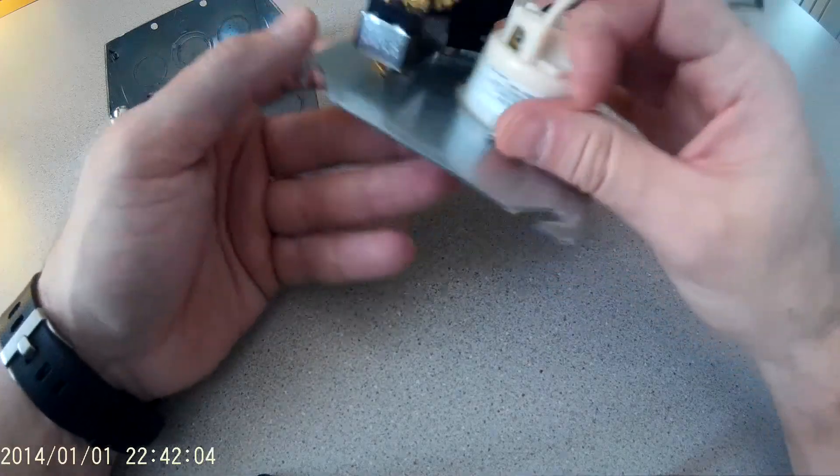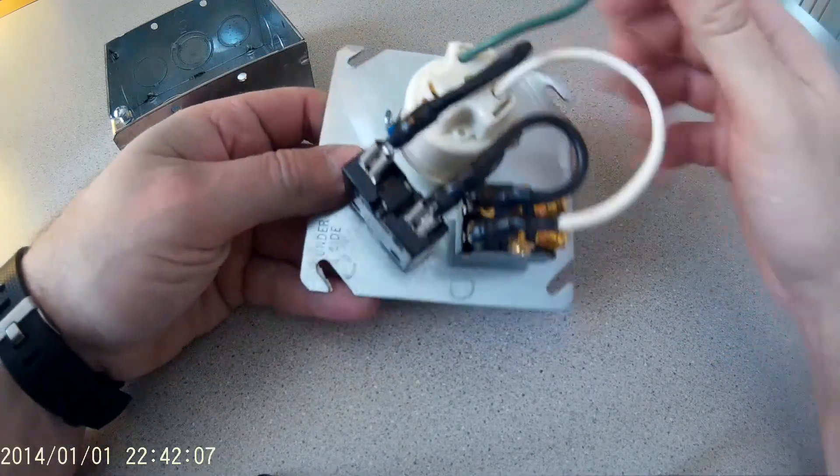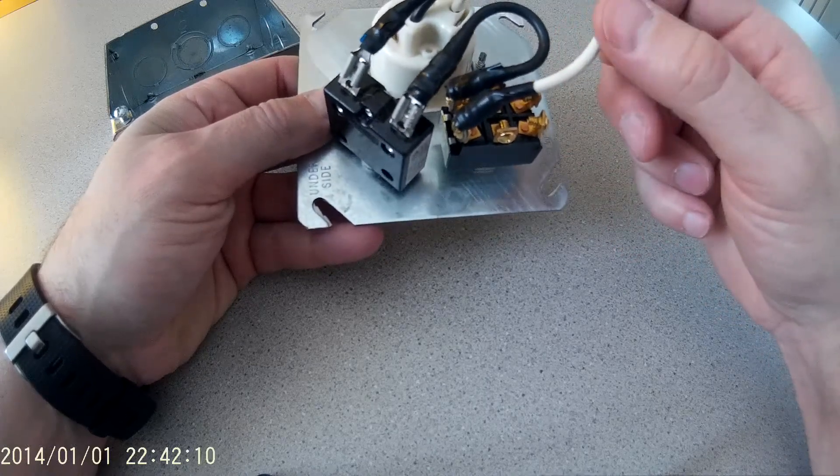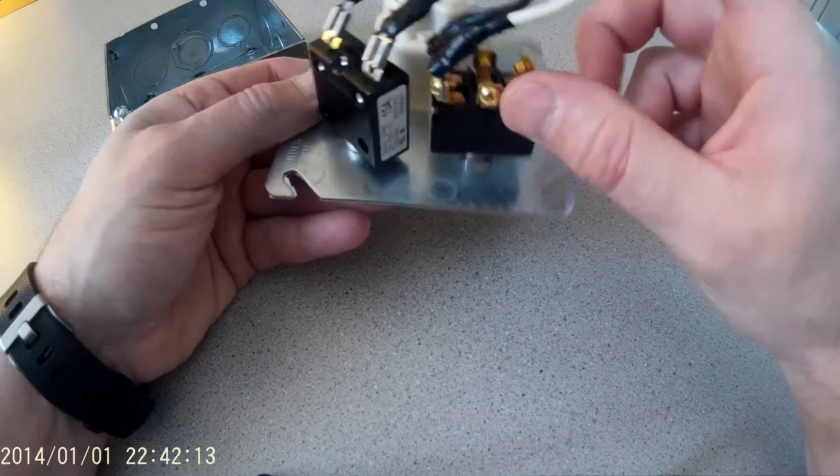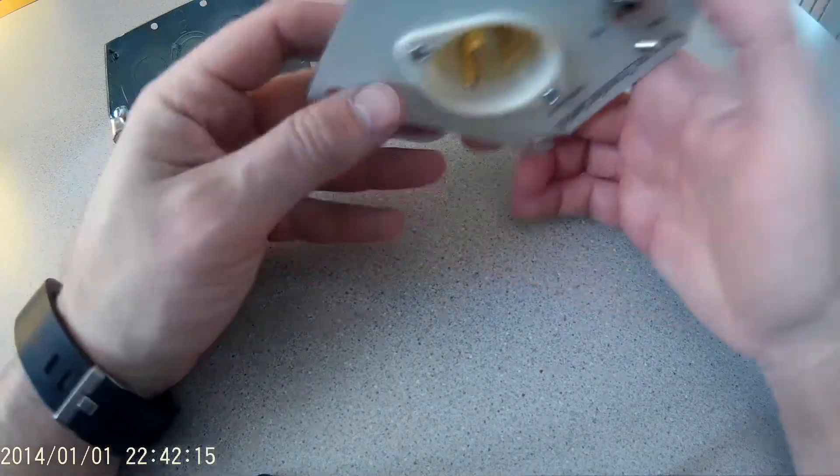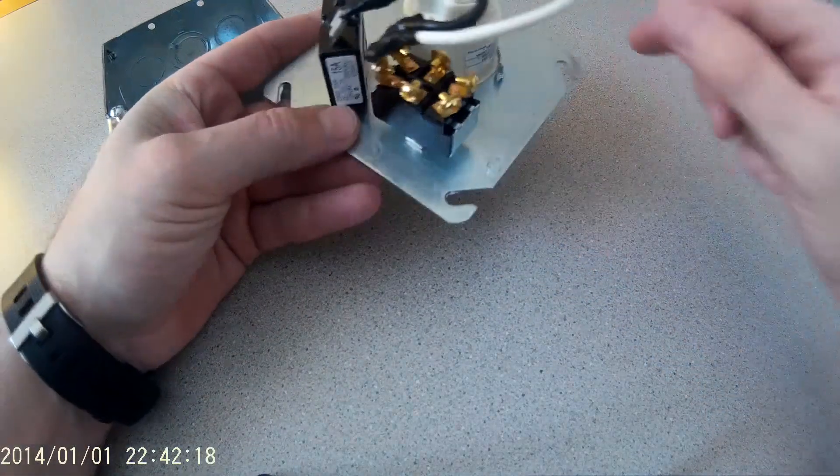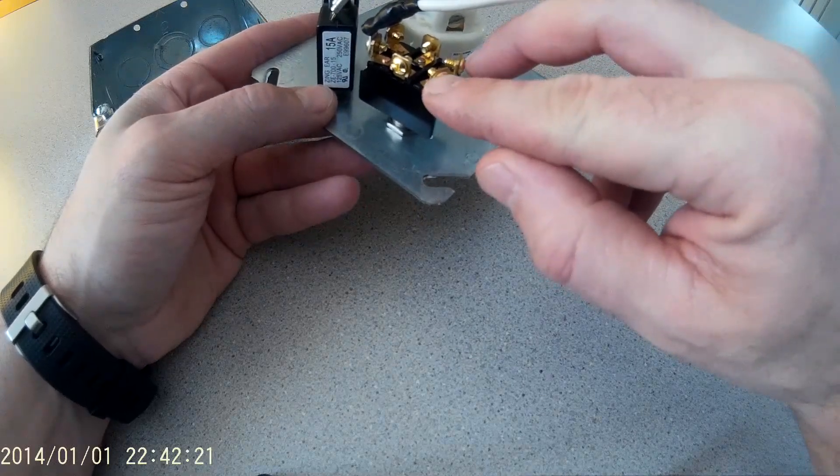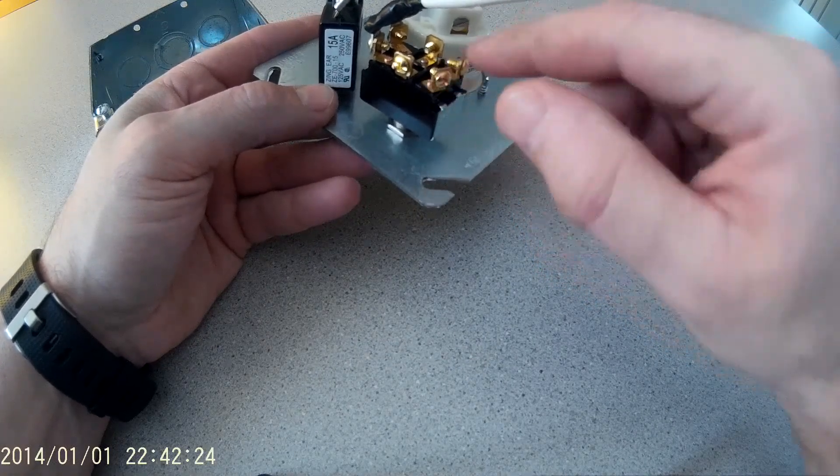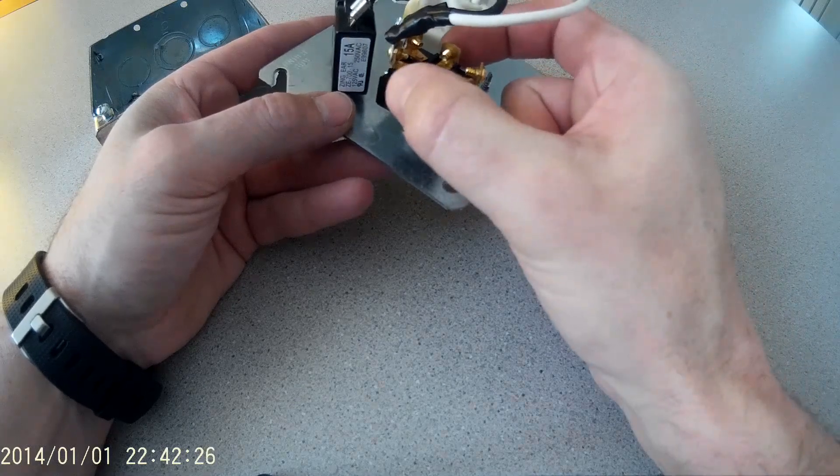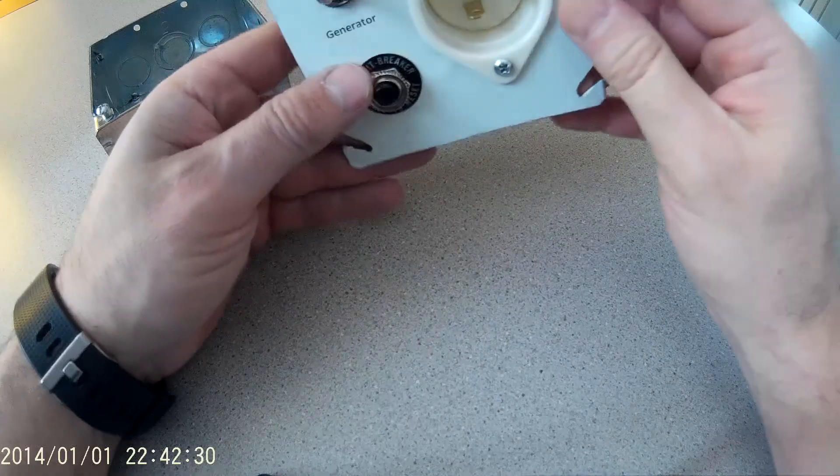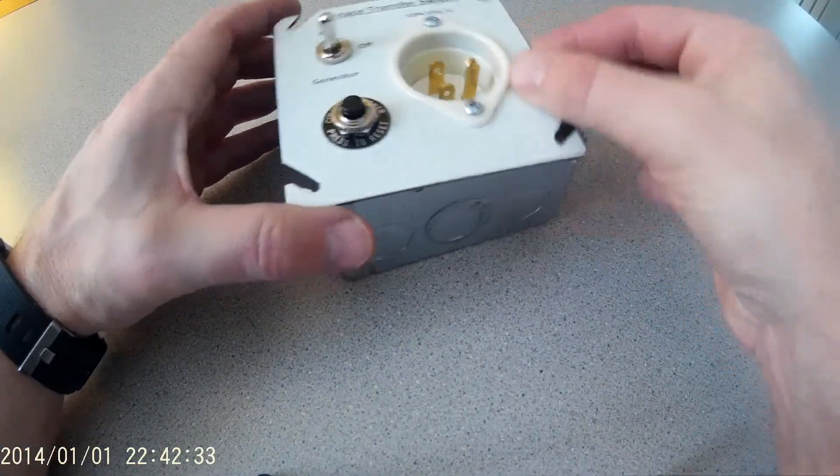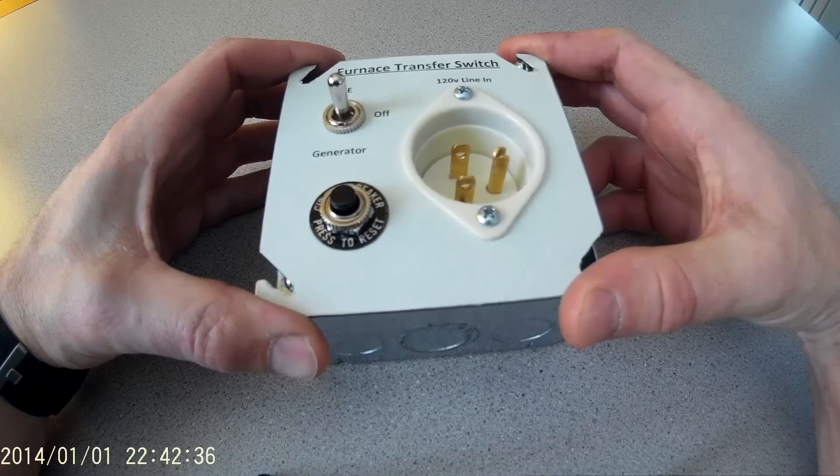On the back, you can see I just got a ground wire. Our neutral goes right to the double-pole, double-throw switch, and the hot wire is running through the circuit breaker. So all I'm going to do is wire in my line hot and neutral to these two poles of the switch, and then these two terminals will be the feed for the furnace, and I can mount everything all up and close it up and test it, and we'll be done.